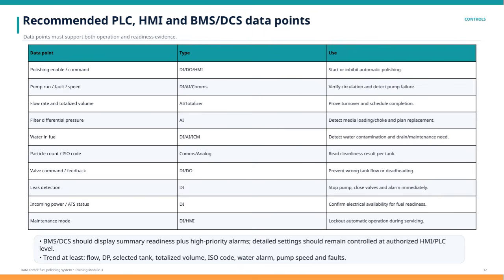Measuring particle count or ISO cleanliness codes through communications or analog signals informs us about the fuel's cleanliness level in specific tanks. Valve commands and feedback prevent incorrect tank flow or deadheading that could damage the system. Leak detection is critical. It must immediately halt pumps, close valves, and trigger alarms to prevent spills or system damage. We also monitor incoming power and automatic transfer switch status to confirm electrical availability, ensuring the fuel system is always ready. Finally, maintenance mode allows operators to lock out automatic functions during servicing, protecting both personnel and equipment.